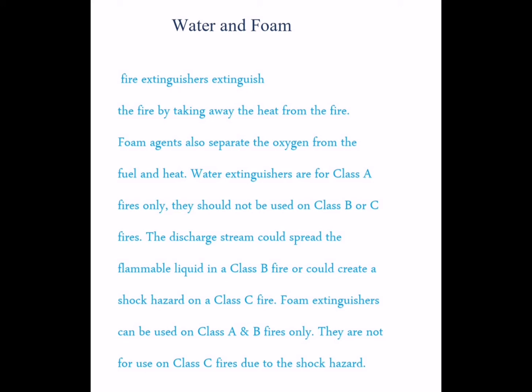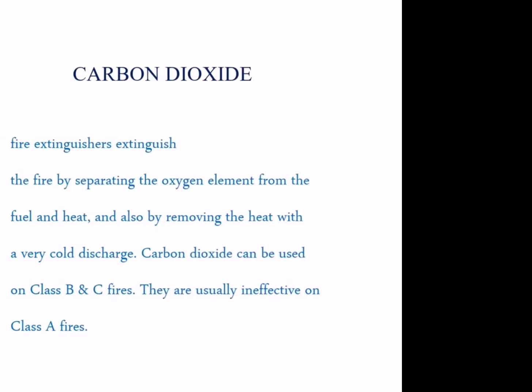The discharge stream could spread the flammable liquid in a Class B fire or could create a shock hazard on a Class C fire. Foam extinguishers can be used on Class A and Class B fires only. They are not for use on Class C fires due to the shock hazard.